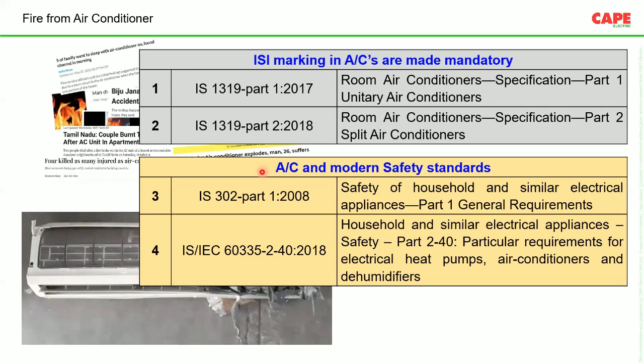There are some additional standards with respect to safety. For example, IS 302 part 1, which talks about the safety of household and similar electrical appliances. This 302 is actually a mandatory requirement for all electrical appliances which are used, and this 302 again is from IEC 60335 part 2-40. There is an IS standard, 2018, which specifically requires additional safety measures for air conditioners.